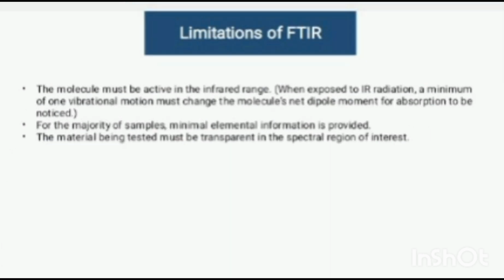scale. Last content of this topic is the limitations of FTIR, and the limitations are that the molecule must be active in the infrared range. When exposed to IR radiation, a minimum of one vibrational motion must change the molecule's net dipole moment for absorption to be noticed. For the majority of the samples, minimal elemental information is provided. Material being tested must be transparent in the spectral region of interest.